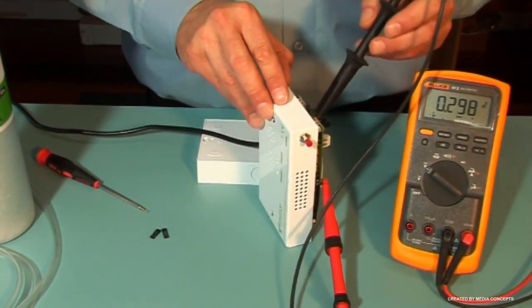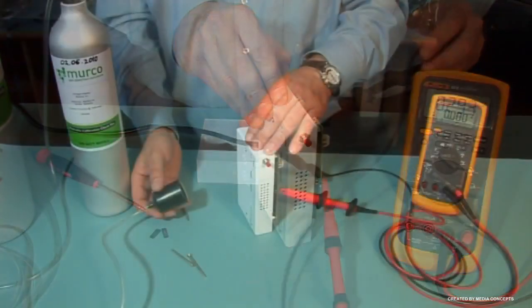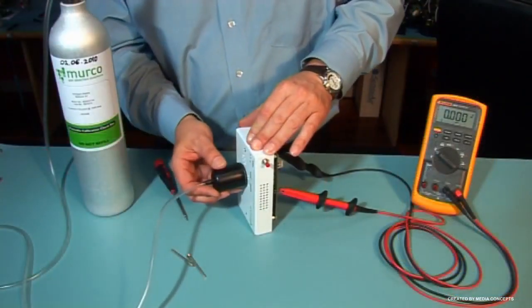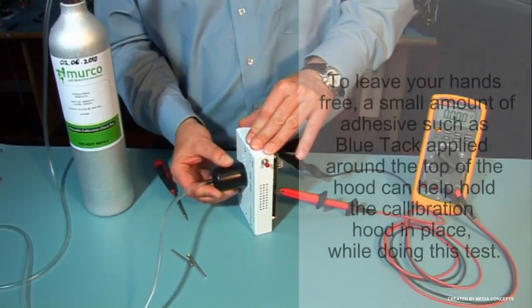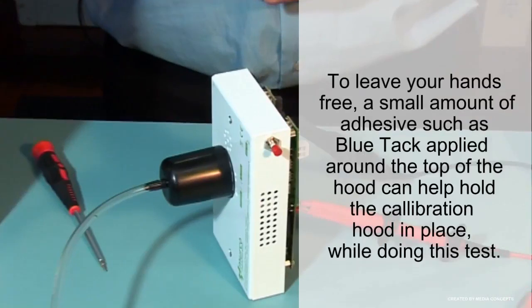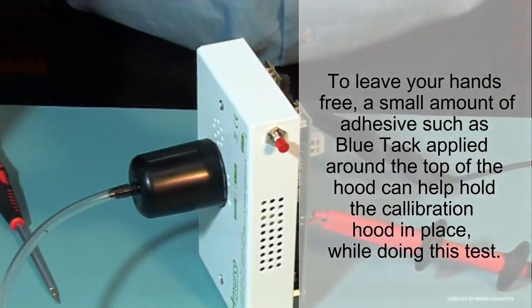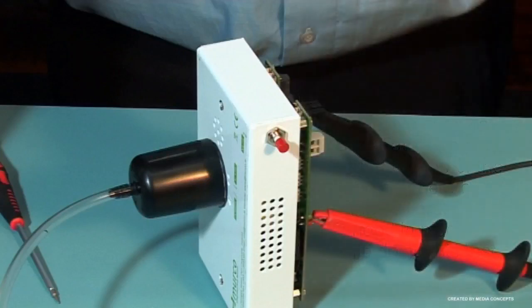Having carried out the electrical setup, expose the sensor by introducing gas through the front panel here. You should see the standby voltage increase. It may take 10 to 15 minutes to pass the alarm through this set point. Older sensors may take longer. Once you've reached the alarm set point, the red LED will light and the sounder, if enabled, will activate.